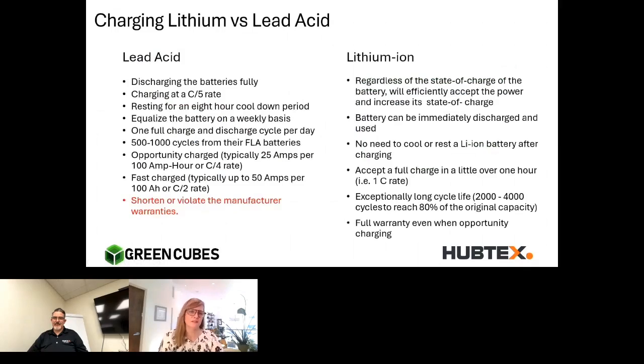The recommended charging algorithm for lead acid batteries is a C/5 rate, meaning a 5-hour charge time to 80% capacity, followed by an 8-hour cool down period, and the battery must be equalized on a weekly basis. That translates to basically one full charge and one full discharge every day for a lead acid battery used in its recommended charging algorithm.